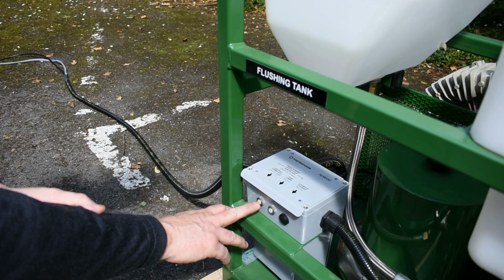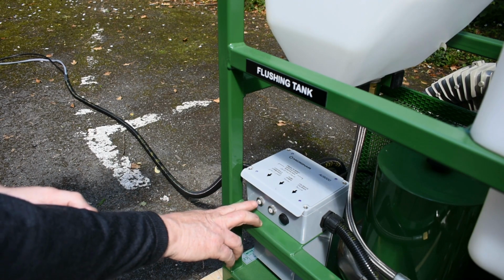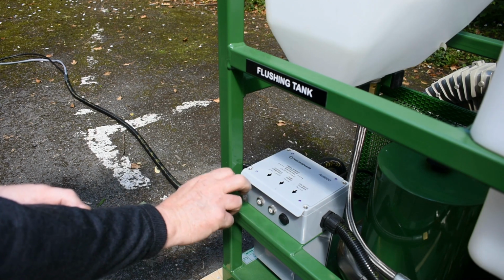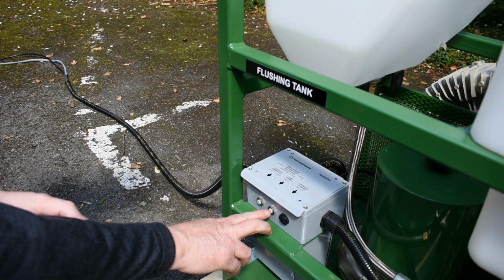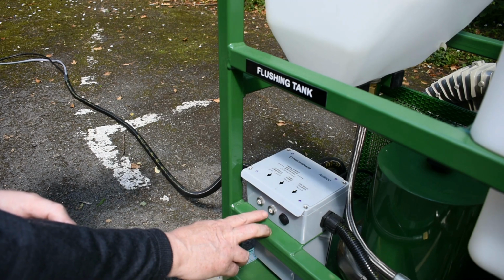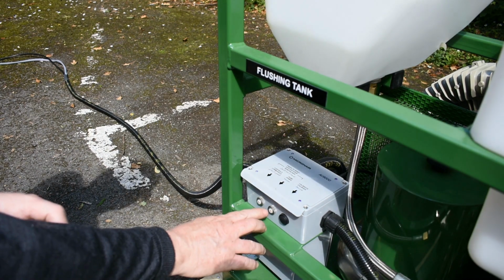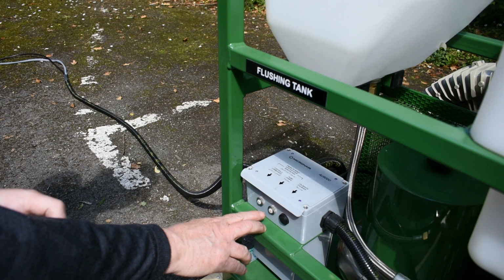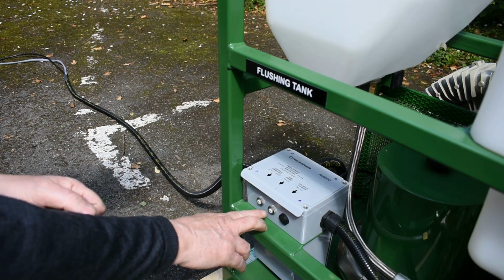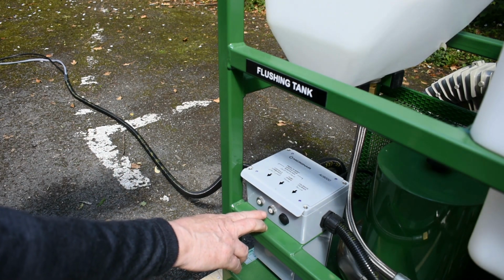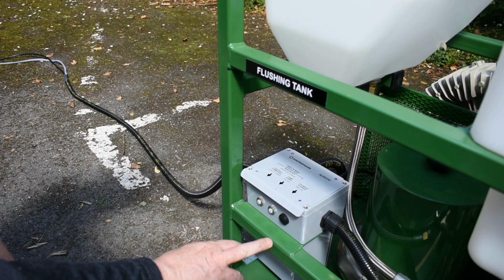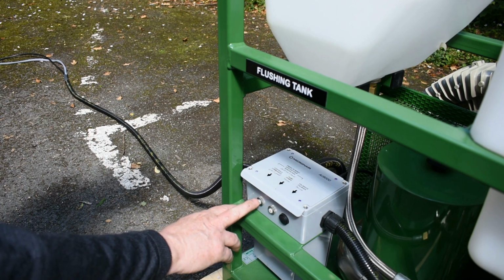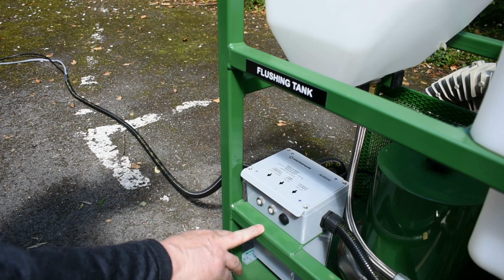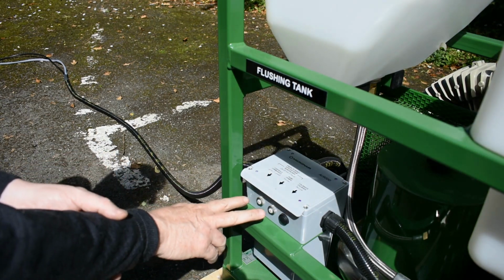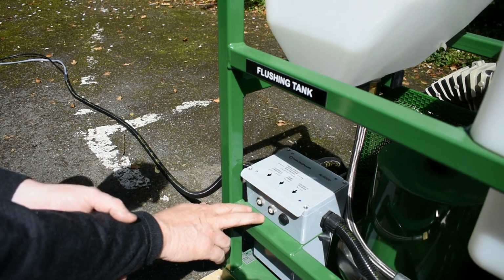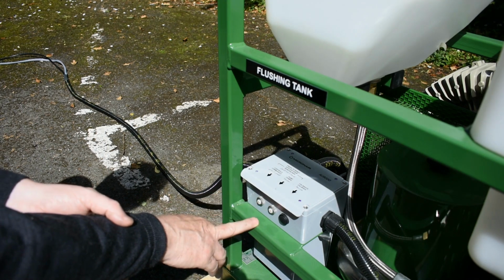There's a 5 amp fuse here, which is a resettable fuse should there be a problem with the control unit. There is a 15 amp fuse which again is resettable. It would pop out if there was a problem with the pump. That could be through a blockage or a fault somewhere on the pump, or even a wiring issue. The important thing here is always to check these are actually in position. So these are the two circuit breakers for the pump and the control unit.